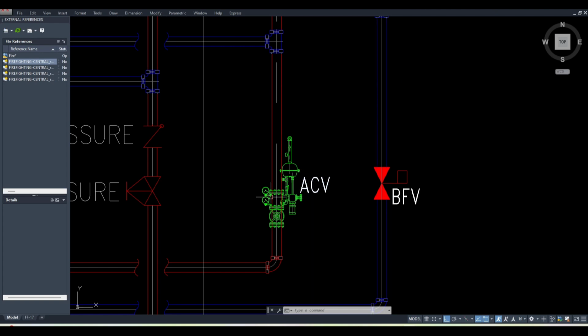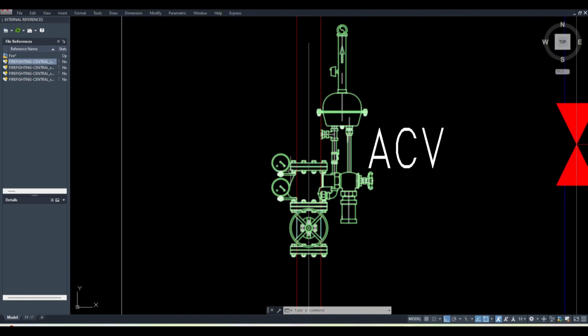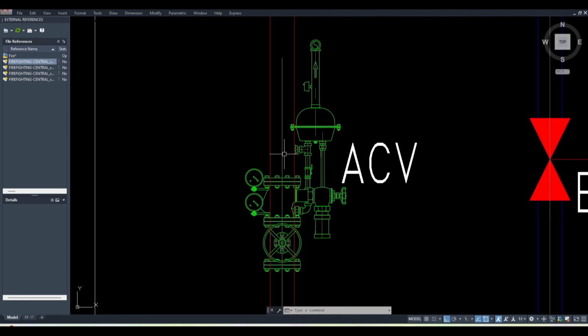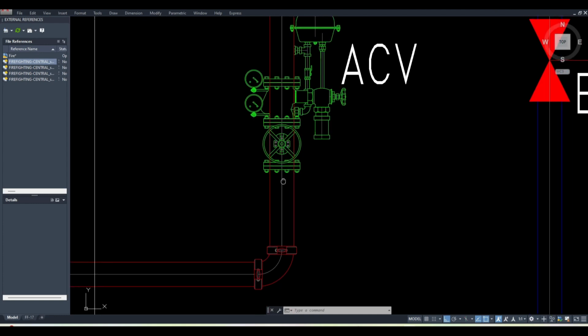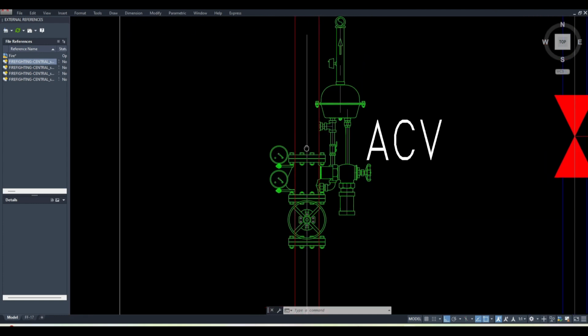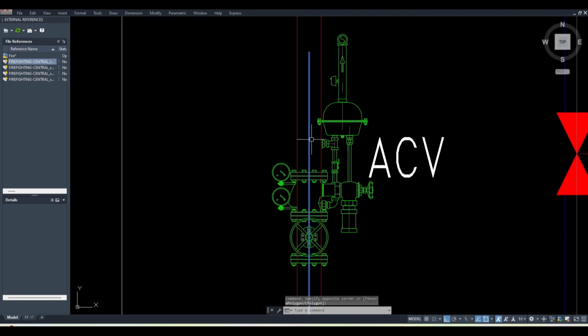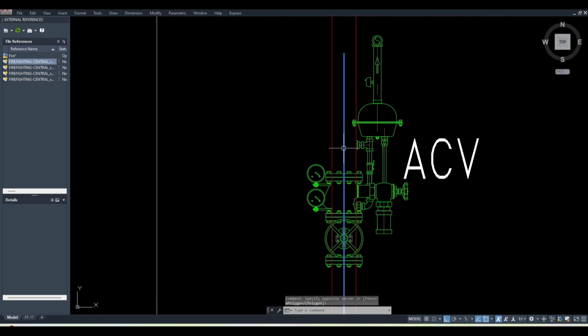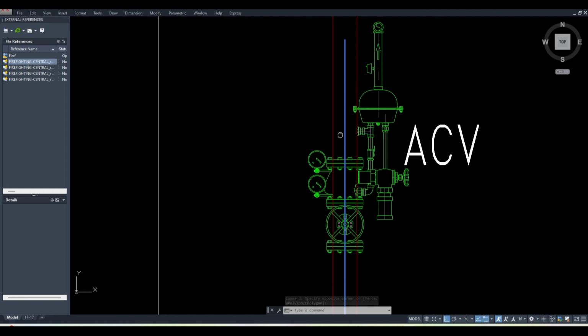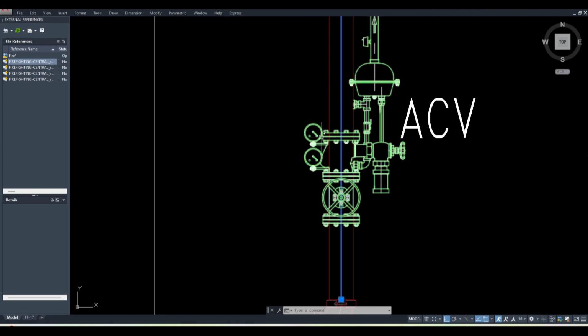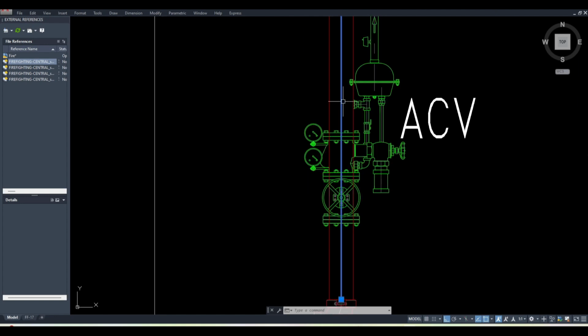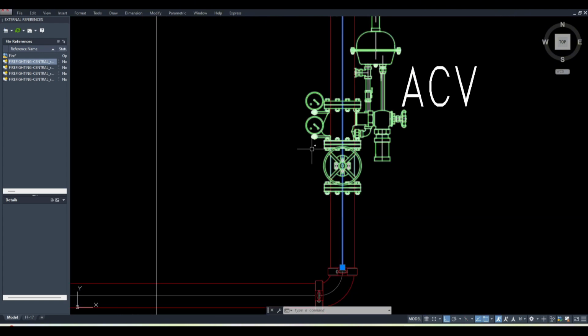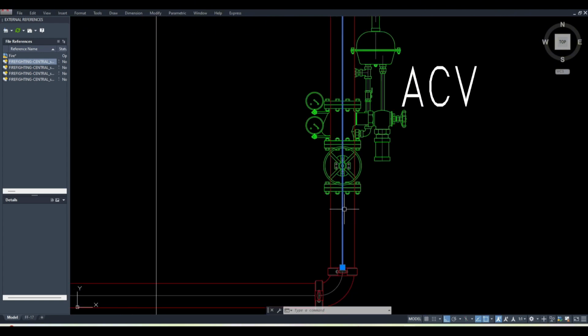Another thing is, there are two pressure gauges in this alarm check valve. One checks the pressure of the front side, and one checks the back side, okay. So differential also it can measure. So for example, suppose there is a pressure, okay, if it is less than the required pressure, then this will give you a signal that this line has less pressure, okay. And also, if there is no water on this side, then also it can give you the signal. So we can know whether the pressures on both sides are there or not, the required or whatever we want, okay.